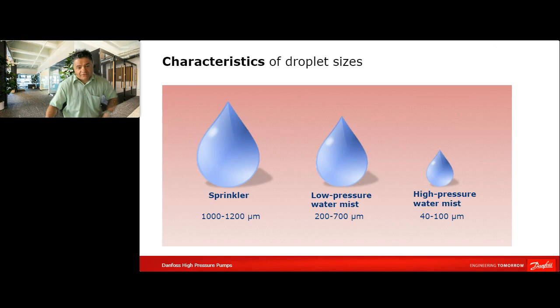When we look at the droplet sizes and compare the technologies with each other, a sprinkler droplet has a diameter of around 1 to 1.2 millimeters. 1000 microns is equal to 1 millimeter. When we put the water more under pressure and come to the low pressure water mist level, we talk about a droplet diameter of 0.2 to 0.7 millimeters. And when we push it further under pressure and come to the high pressure water mist range, we have 0.04 to 0.1 millimeter for each droplet. So you can see the higher the pressure, the smaller the droplet diameter.